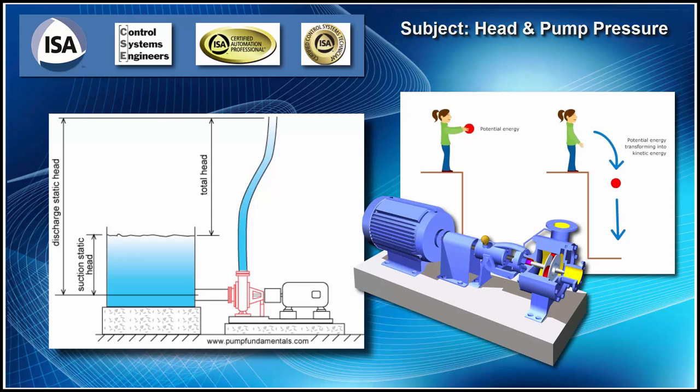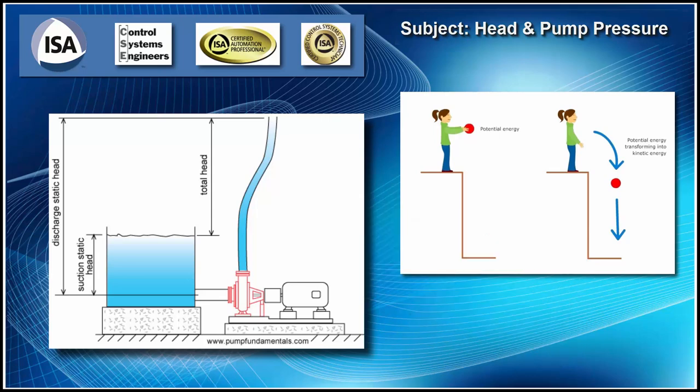Now, remember, as you cause this vacuum, there is no pressure there. Therefore, the pressure outside, the weight of the water, or if it's below the pump, the force of the air, forces that water up in here, because the air is 14.7 psi. So 14.7 psi would be 33.9 feet of a column of water. And so it's just like having a tall column of water pushing down and trying to push it up in here. In other words, the air is doing work on the water and forces it up into the pump. Since there's no resistance, because there's vacuum, there's no molecules, so it tries to push those molecules into the pump. And that's how the pump starts circulating the water.